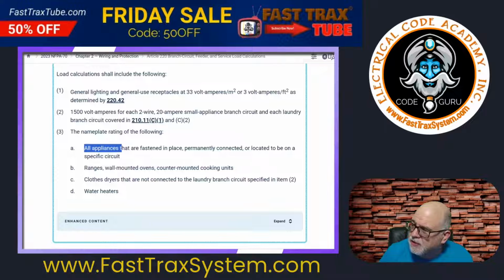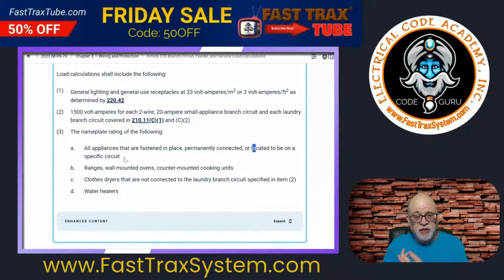All appliances that are located on specific circuits. So this would pick up all those things like your air conditioning, your heating. Those are appliances and they're on specific circuits for those loads. This would also be where you would pick up anything like an EV charger or something like that, which you're taking at the nameplate, and all this other stuff. Okay, you're picking up all of these loads under this method.